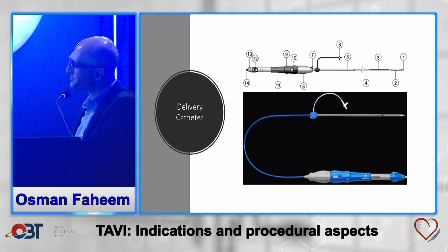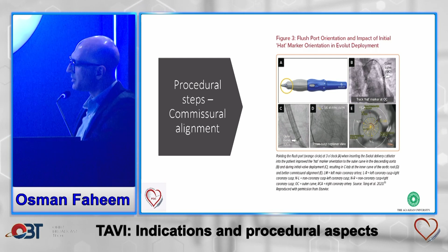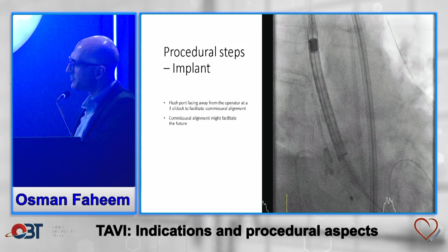You inspect the valve under fluoroscopy. Make sure the paddles are good and symmetric. Here you can see there's more separation between this paddle than this, so it's asymmetric and the valve needs to be reloaded. The other thing when you go up is to keep this port at the 3 o'clock position, because that minimizes the chances of your valve or the commissure obstructing the left coronary.